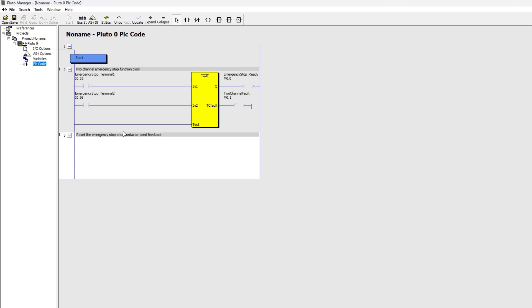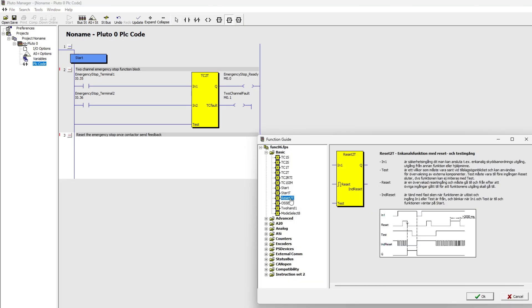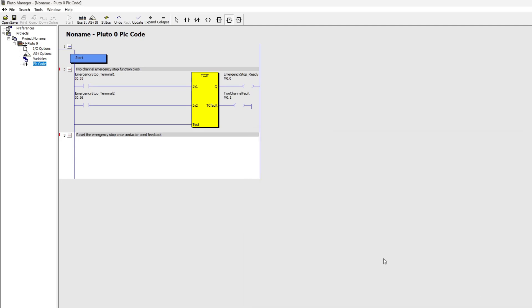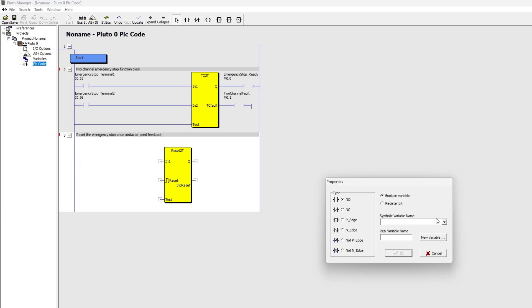In the second rung of code I am going to add a two-channeled reset function block. To the first input I will connect the memory bit that makes sure the emergency stop is ready from the previous block.